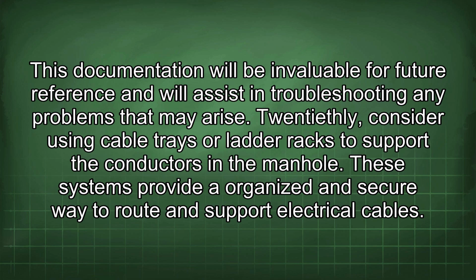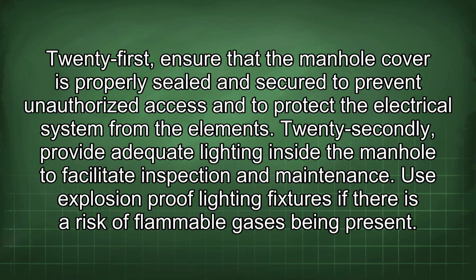20thly, consider using cable trays or ladder racks to support the conductors in the manhole. These systems provide an organized and secure way to route and support electrical cables. 21st, ensure that the manhole cover is properly sealed and secure to prevent unauthorized access and to protect the electrical system from the elements. 22ndly, provide adequate lighting inside the manhole to facilitate inspection and maintenance. Use explosion-proof lighting fixtures if there is a risk of flammable gases being present.